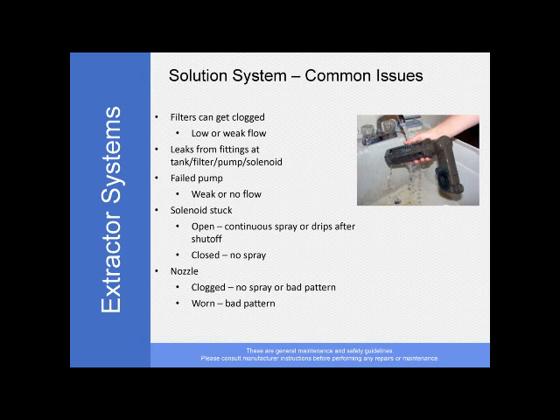The nozzles can get clogged. You'll have no spray or a bad spray pattern. Instead of that nice fan shape, you'll get spray off to one side or huge clumps of water out the middle. And if they're worn, you'll also get a bad pattern. They're usually a soft brass, and after years and years and years of spraying, that brass actually erodes away. So if you lose your nice tight fan pattern, you get almost like a leaky faucet effect.